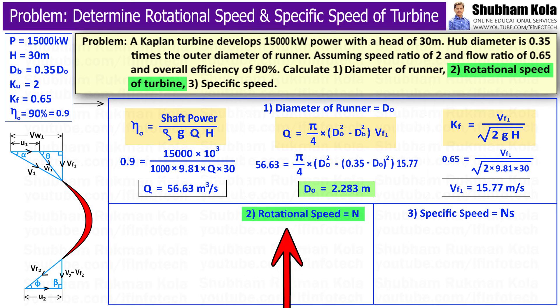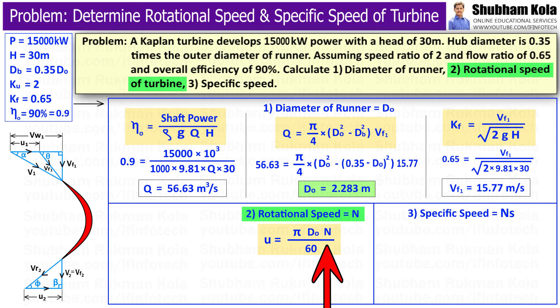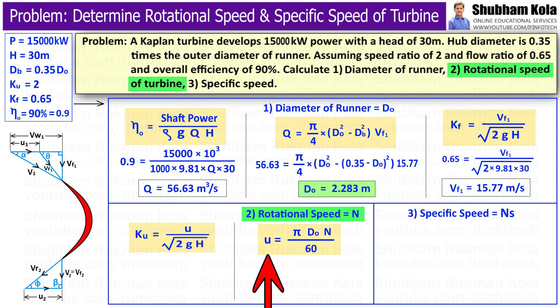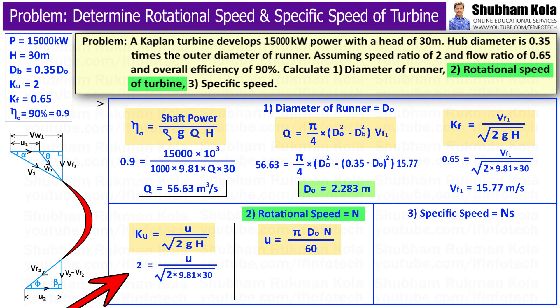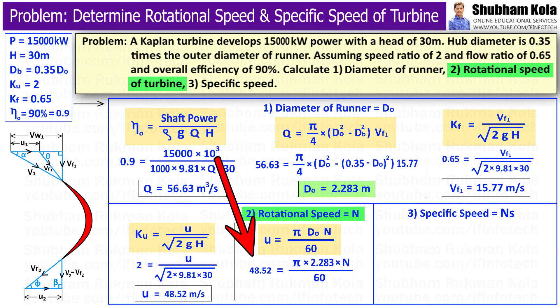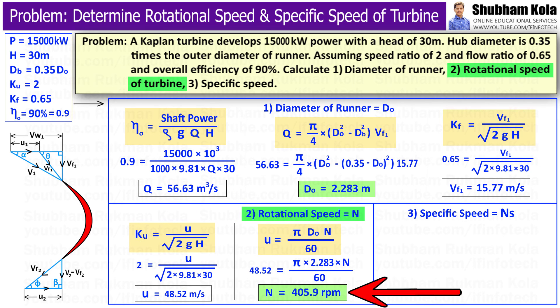Next, we calculate the rotational speed of the turbine, capital N, using the tangential velocity formula: u equals pi × Do × N divided by 60. The tangential velocity u is calculated from the speed ratio formula — speed ratio is 2 and head is 30 meters — giving u equal to 48.52 m/s. Substituting this value, we get the rotational speed N equal to 405.9 rpm.